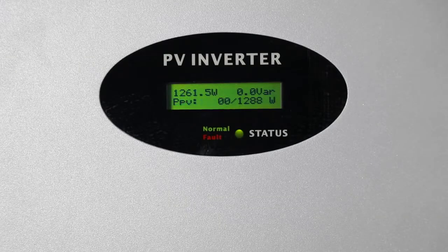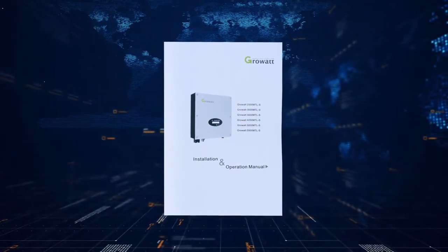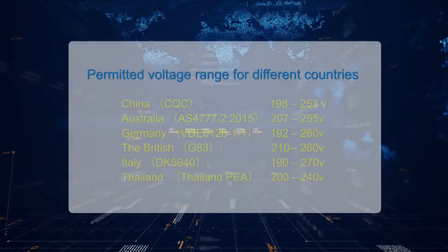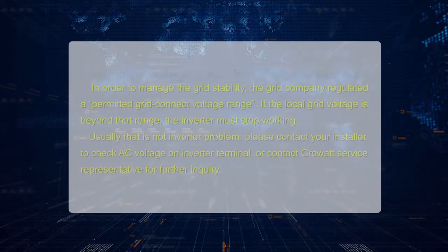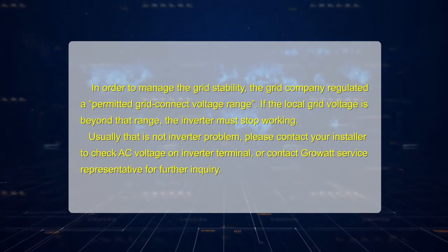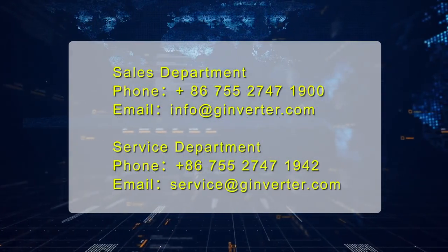The inverter will show an error message or error code on its LCD screen if a fault occurs. Please refer to the user manual for a complete fault list and description. There is also a detailed troubleshooting guide available on the Growatt website. In order to manage grid stability, the grid company regulates a permitted grid connect voltage range. If the local grid voltage is beyond that range, the inverter must stop working. Usually that is not an inverter problem — please contact your installer to check the AC voltage on the inverter terminal, or contact the Growatt service representative for further inquiry.